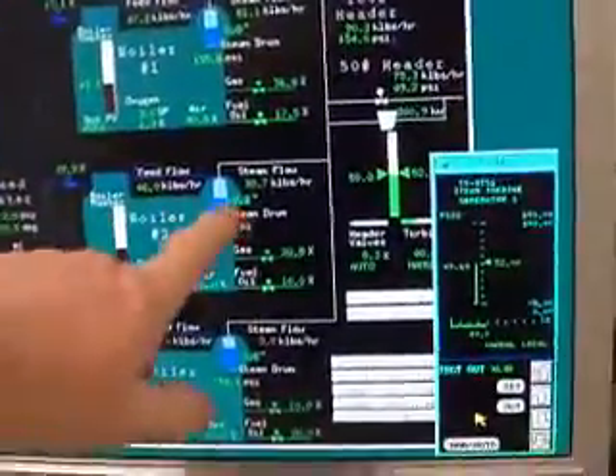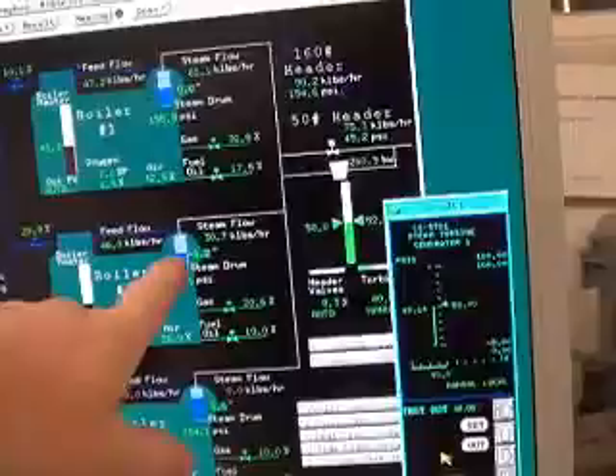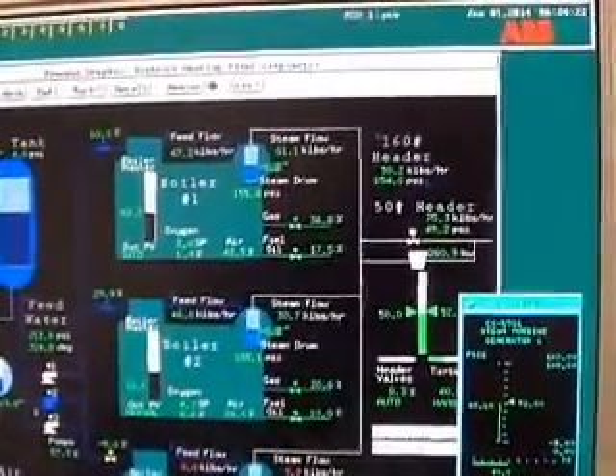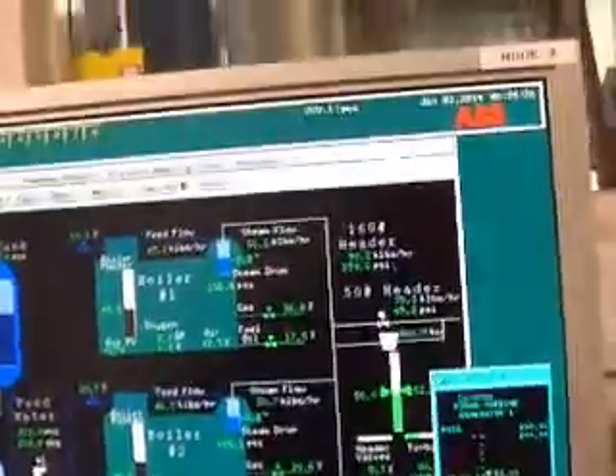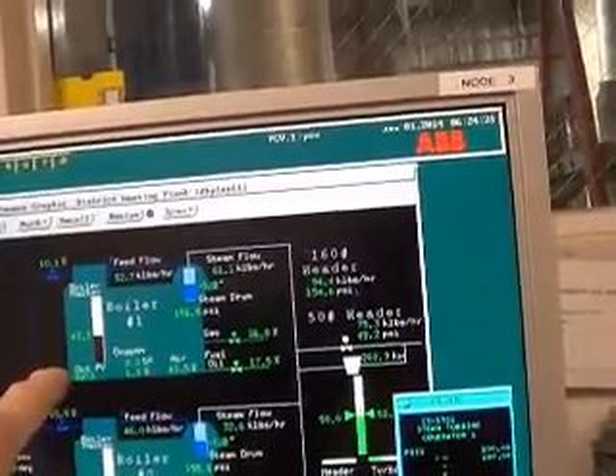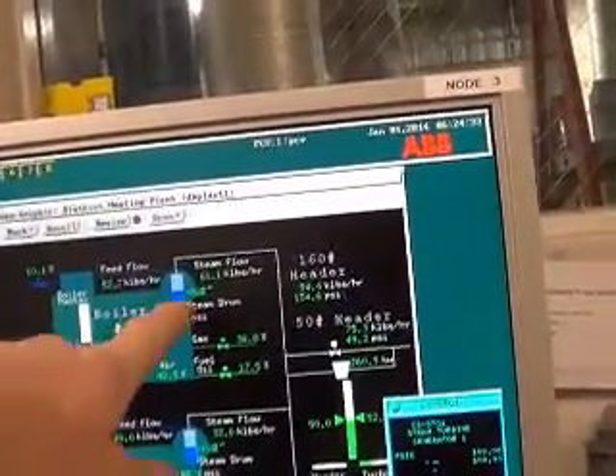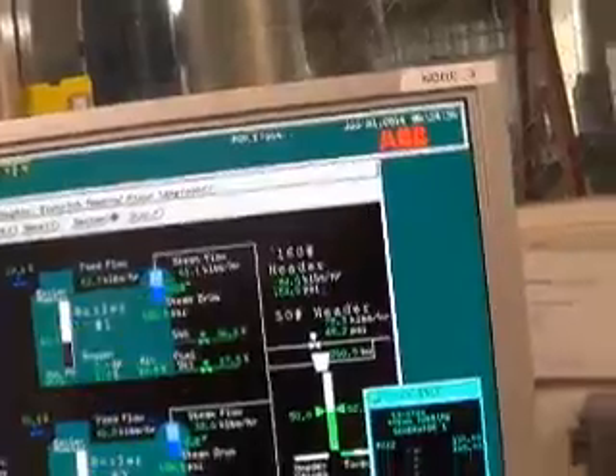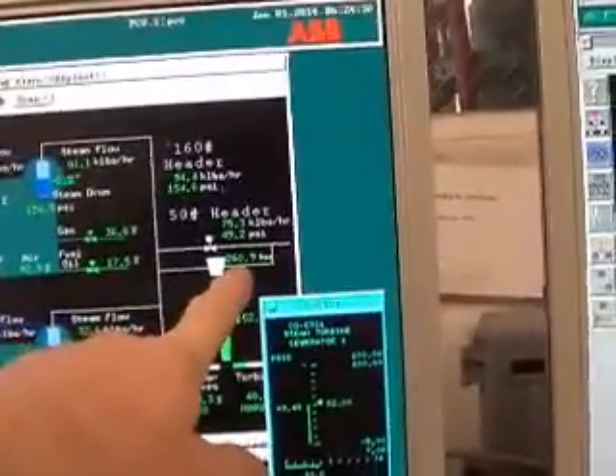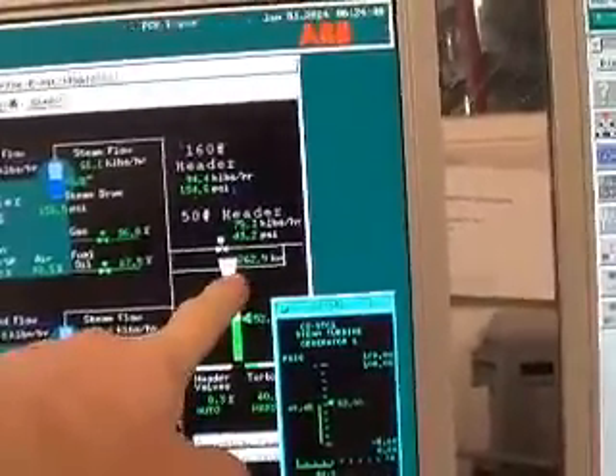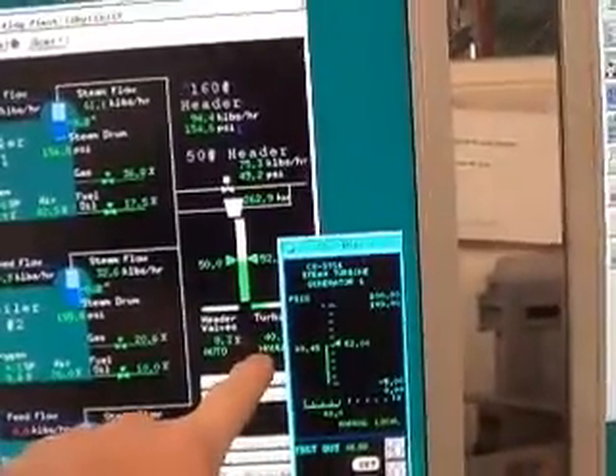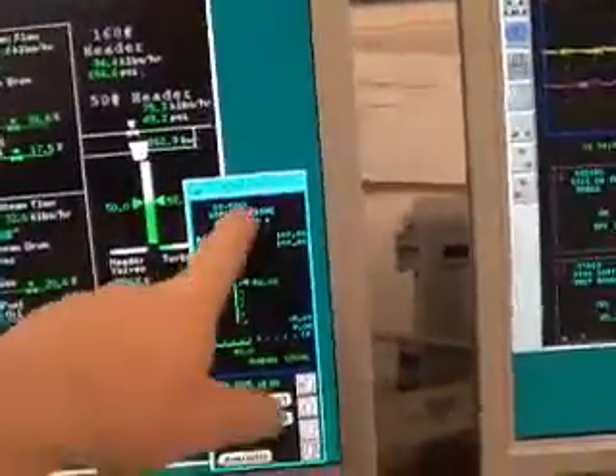So here's a graphic of the boilers. What I'm looking at is the water level in the steam drum. The set point is 0. It's reading -0.2. That's nothing. This is in manual. The other boiler is in auto, and its level is good. This is indicating how much electricity we're making, and the turbine is in manual. Here's the control for the turbine.